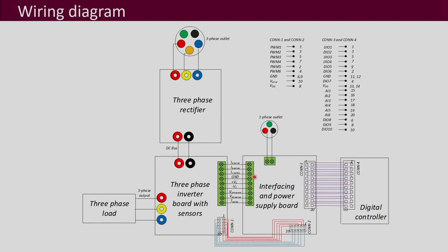So, you have to see whether there is a possible ground loop that is getting formed because of this PCB via these other external connections of grounds that are present. So, you have to be very careful about that. If not inside the PCB, if externally through some connections and through some cables, any ground loop is getting formed or not, that is what you can check through the wiring diagram. Apart from that, ground loops may also be getting formed through the electrical outlets which have got the earth points in them. So, how can that happen? Let us look into it.